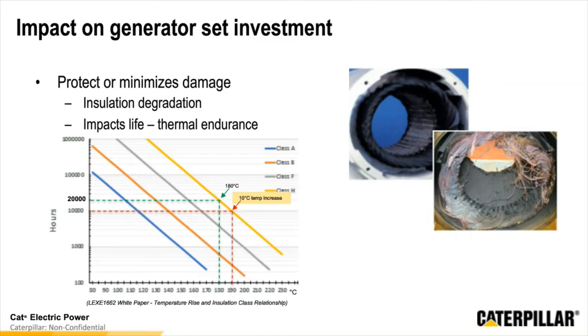So as we said just before the poll question, one of the biggest things that we're looking at is trying to protect that generator set investment. Along with the entire system and making sure that the system stays up, we're looking at our generator set as a large asset within our standby power system, and we want to make sure that we get the most out of that investment. One of the things that we're looking at is that as current flows through a wire, it generates heat. And over time, that heat will degrade the insulation within our generator sets. Each different generator may have different classifications of insulation material, and that different classification will have different life expectancy based off of different temperature ranges.